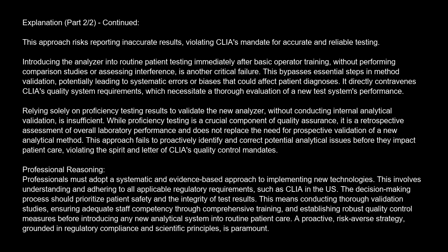Relying solely on proficiency testing results to validate the new analyzer without conducting internal analytical validation is insufficient. While proficiency testing is a crucial component of quality assurance, it is a retrospective assessment of overall laboratory performance and does not replace the need for prospective validation of a new analytical method. This approach fails to proactively identify and correct potential analytical issues before they impact patient care, violating the spirit and letter of CLIA quality control mandates.